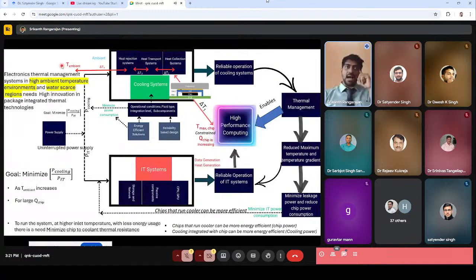Now if you want an aggressive thermal resistance target of, say, 0.03 Kelvin per watt, you have to make sure the heat collection systems are well optimized so they can operate at very low thermal resistance. This also emphasizes one more thing: if you have a power supply entering a data center, it's consumed by two main components—the IT systems and the cooling systems. So if you want your IT system, like your electronic chip, to operate reliably, it's well understood that only if your cooling systems are reliable can your IT systems be reliable.